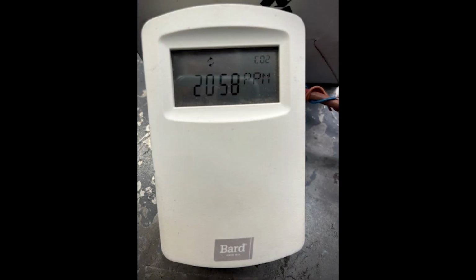There are 2 choices with a CO2 sensor control method with this classroom ventilator. Fixed position damper, open and closed when A is energized, while the other method, the damper will modulate with a 2 to 10 volt DC signal. We suggest you contact your BARD territory sales manager to assist you with a wiring drawing and setup details for the CO2 sensor method.